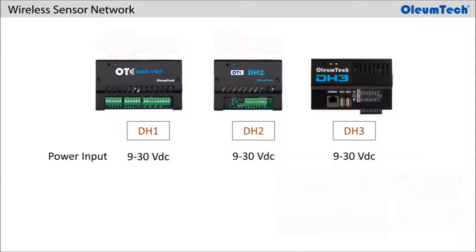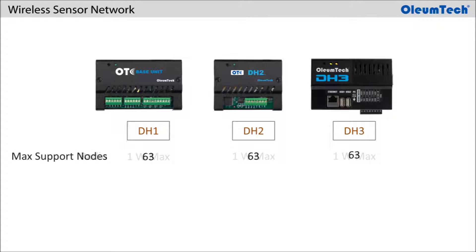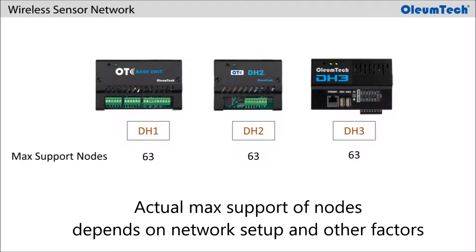As for the similarities, all gateways support 9-30 volt DC input power and are equipped with adjustable 1 watt max radios. They have the ability to support up to 63 nodes, and the actual number of nodes supported will be based on the RF bandwidth and throughput depending on the transmission intervals, data packet sizes, and complexity of the networking architecture. They all support Modbus master and slave function.